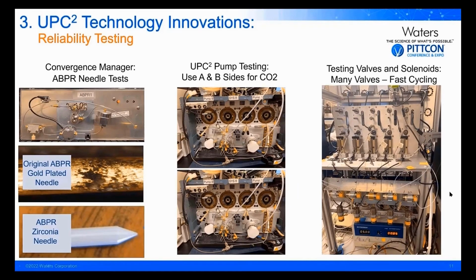Another area that's very important for chromatography systems and specifically for UPC² was the amount of solenoids and valves. So the way we did testing is we put multiple valves and solenoids into one test station, and instead of cycling every few minutes, we actually cycled every few seconds. We did this 24/7 to check reliability and the sustainability of the system over time. This is just some of the testing that goes on during the creation of an analytical LC or SFC instrument.